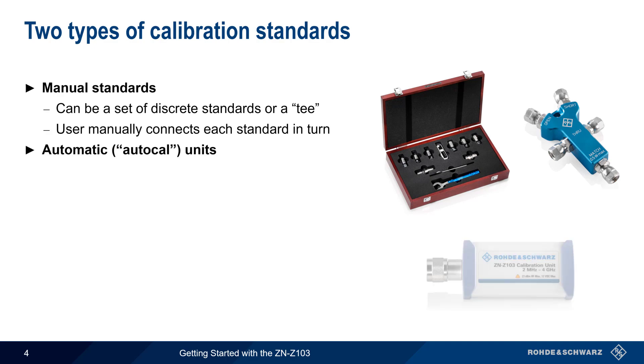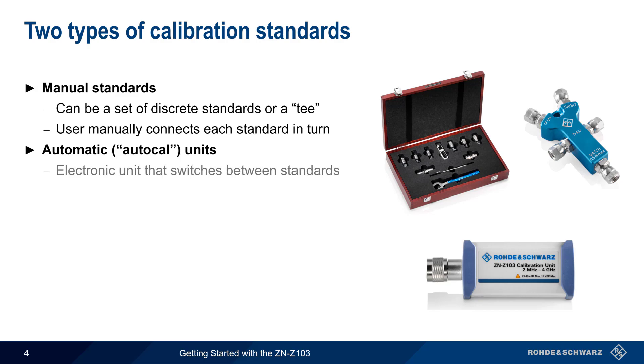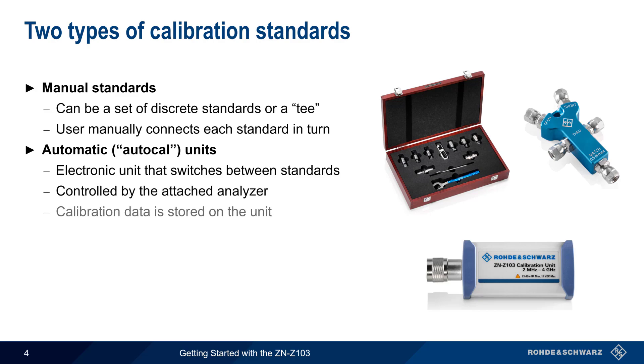The other type is automatic calibration or Auto-Cal units. These are electronic units that switch between a set of internal standards, and this switching is controlled by the connected analyzer. In addition, calibration data is stored on the units and can be read out by the attached analyzer as well.